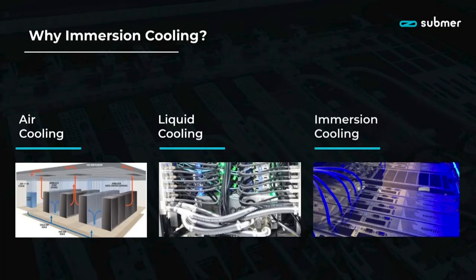Direct-to-the-chip cooling is a technology that pushes water directly through the hot components in a server. It has its challenges. I think the image is very descriptive of some of them: a substantial amount of pipe work and risk of leaks, and those leaks being a conductive liquid like water. But the rack densities can be increased. The cost is not too far off compared to air cooling environments, and it has quite a few benefits, of course, around energy capture and energy reuse, etc.